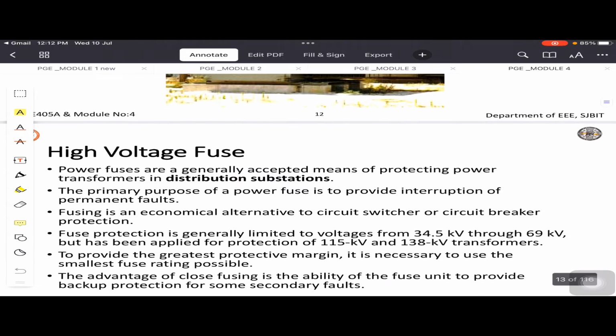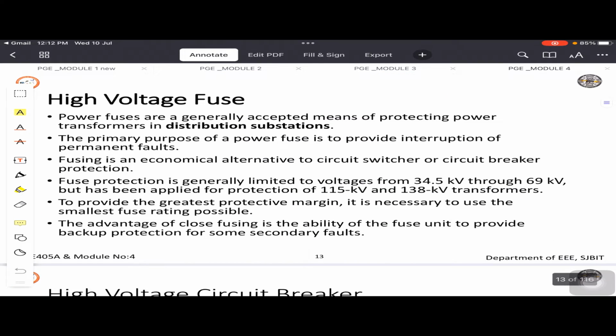Next is the high voltage fuse. We all know that a fuse is a device generally used for the interruption of an electrical circuit in case of a short circuit or whenever there is an excessive overload. It generally consists of a fusing element in the form of a metal conductor, and also a case or cartridge type body. They generally hold the fusible element, and the part which melts or opens up during the overload is called the fusing element. There are different types of fuses we come across. We have cartridge type HV-HRC fuses, liquid type HV-HRC fuses, and high voltage fuses. So this is how fuses are useful in our substation.